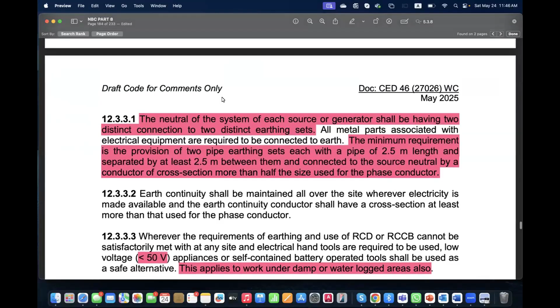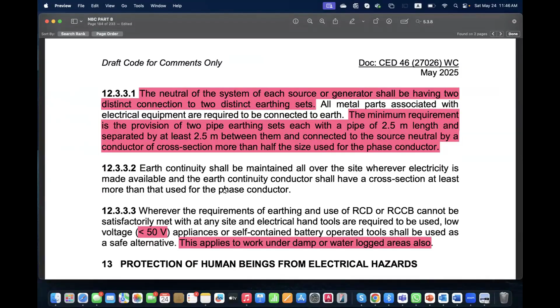There is a requirement in NBC under construction sites that says the neutral of the system of each source or generator shall have two distinct connections to two distinct earthing sets. The minimum requirement is the provision of two pipe earthing sets with a pipe of 2.5 meter length, separated by at least 2.5 meters between them, and so on. This is a big problem because, like Mr. Goswami just mentioned, in IEC there is so much deliberation, if we get stuck on one comment, we add additional days.